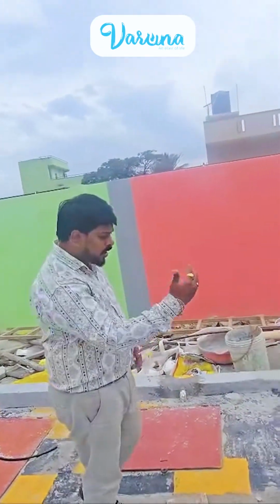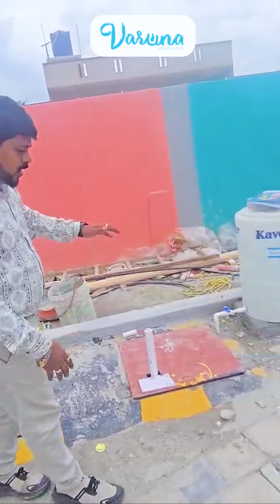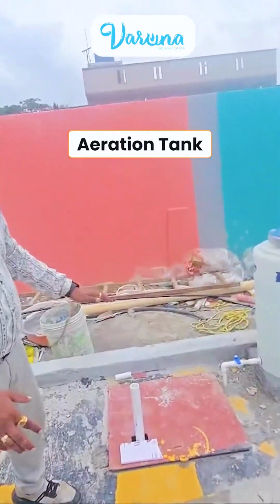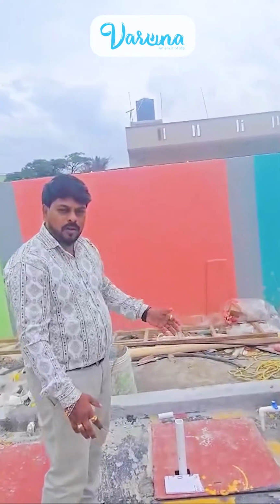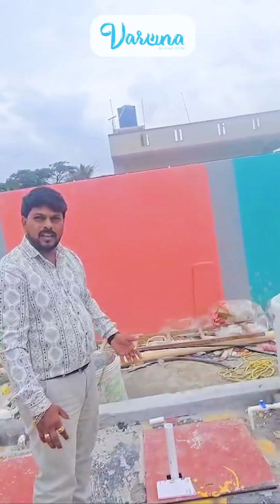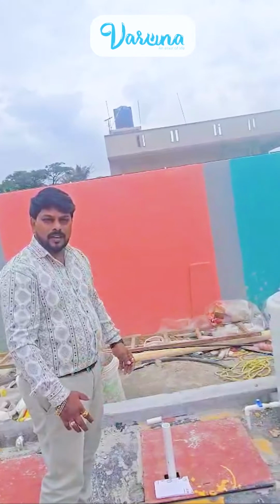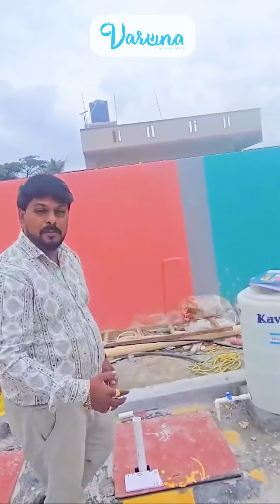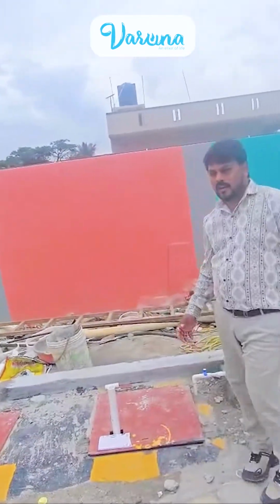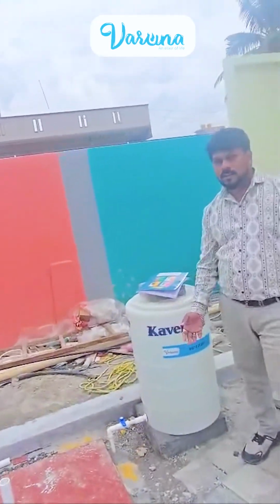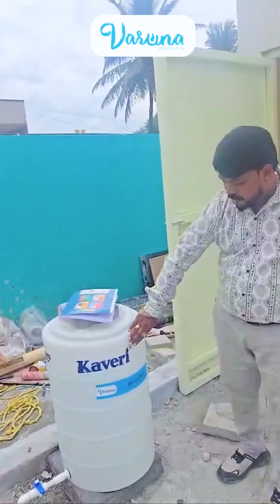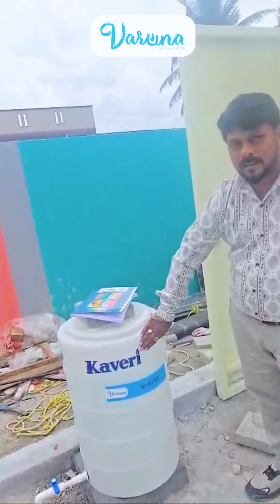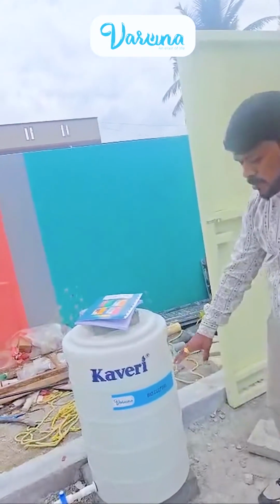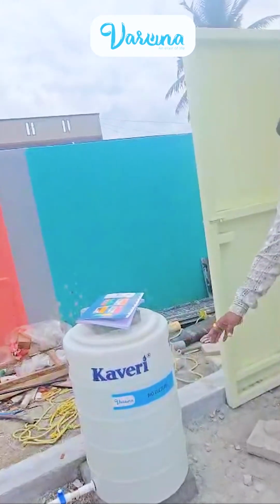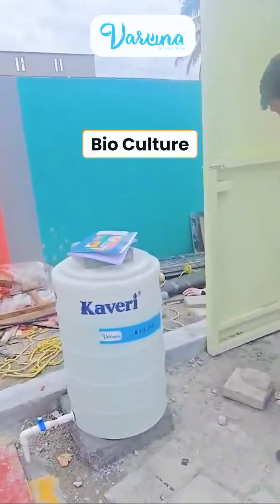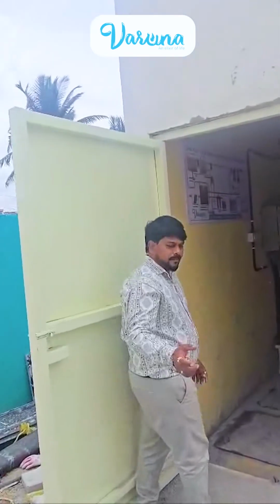The water flows to the next tank, where aeration happens: a huge amount of air is spread into the water. With this, the DO increases, the biological process is enhanced, and with the biological process increasing, we are handling the water's COD and BOD, to bring it to the proper level to maintain the MLSS. So we are adding a bioculture here as a small enhancer.